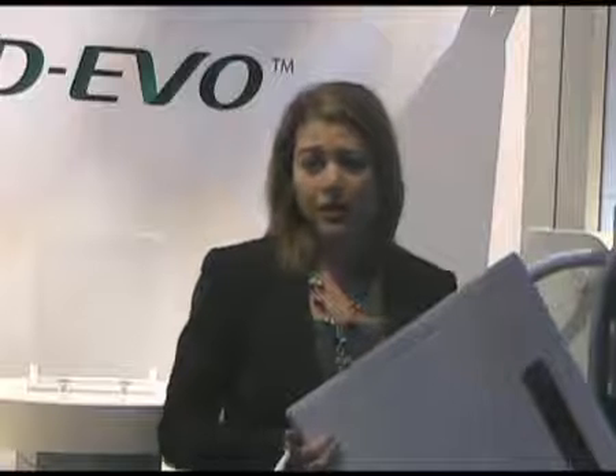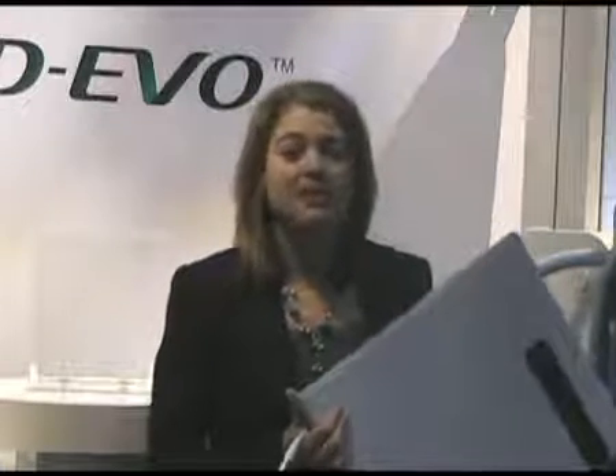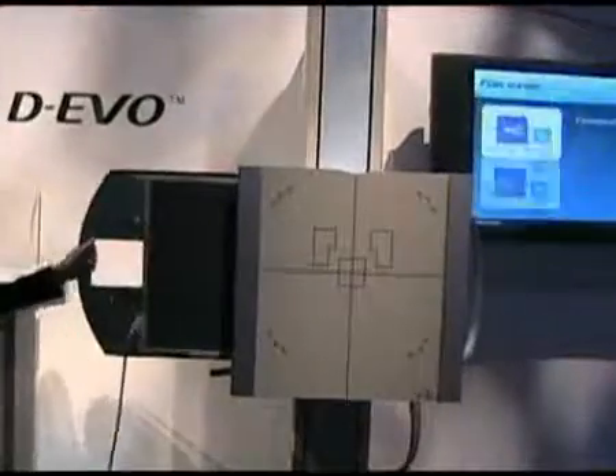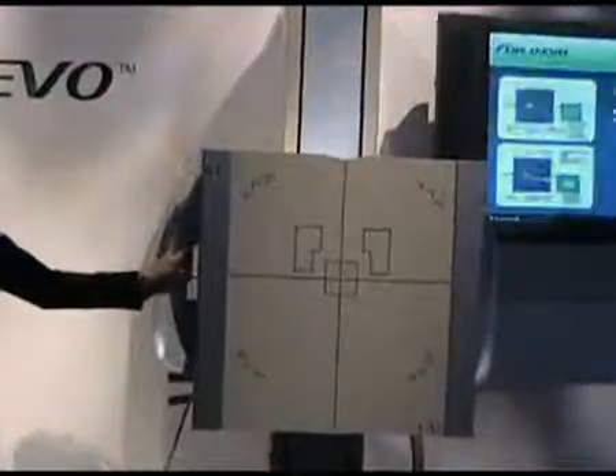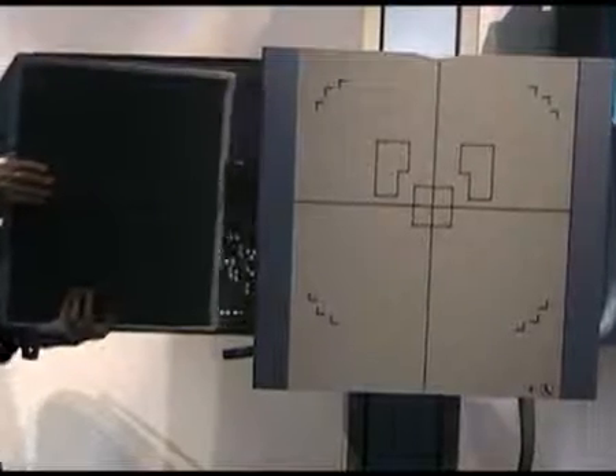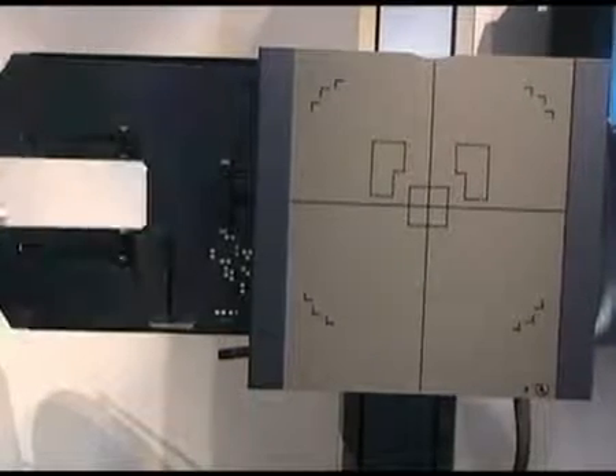Something Fuji has always done is concentrate on image quality, and this product is no exception. What we've done with this product is take the standard gadolinium oxysulfide flat panel detector, but make it better. We've adopted a patented technology called ISS, which stands for irradiation side sampling. In adopting this technology with D-EVO, we've been able to improve DQE and really provide our customers with the same image quality and even improved upon it than what was available before.